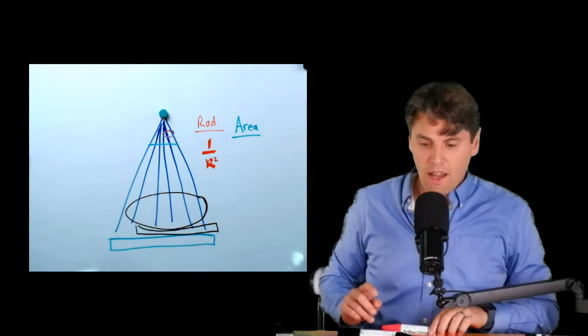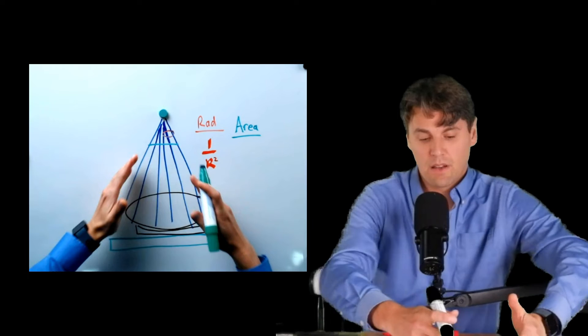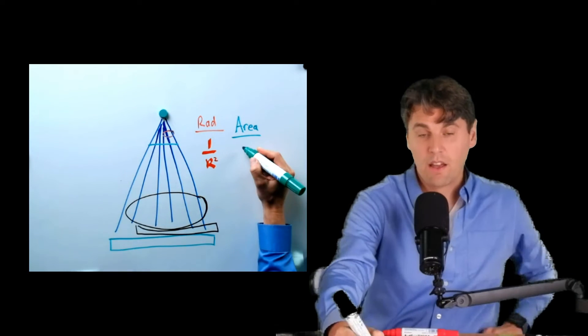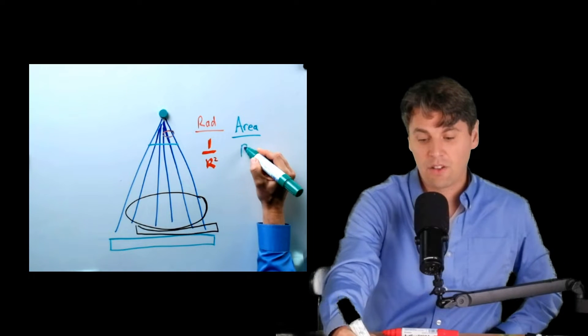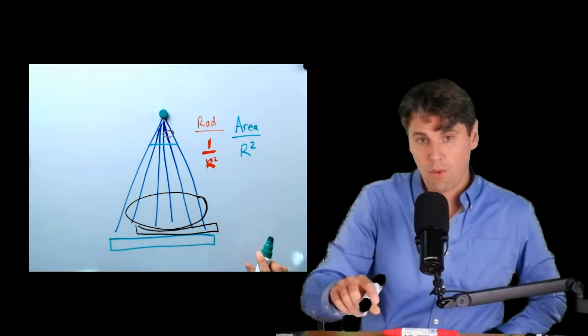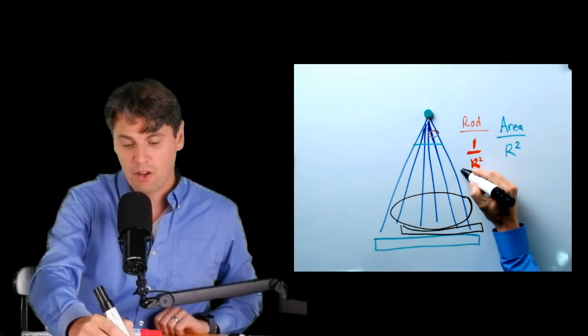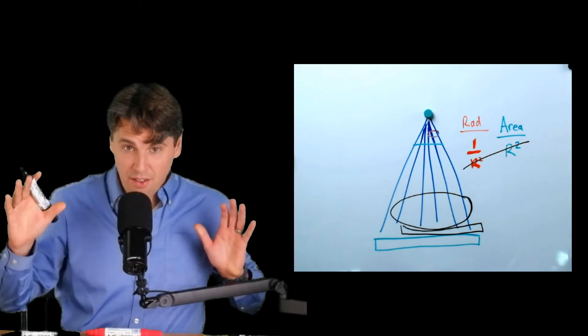And the area, this beam is diverging, so it's going to be covering a larger area. So the area is actually going like R squared. So that is a nice thing about the way that the Kerma area product is developed.